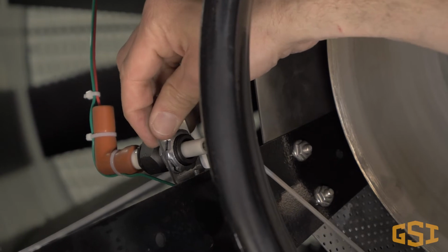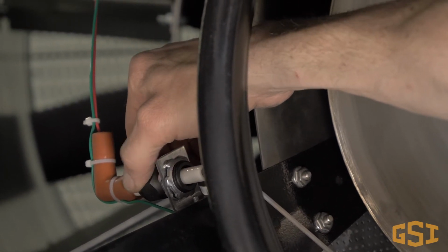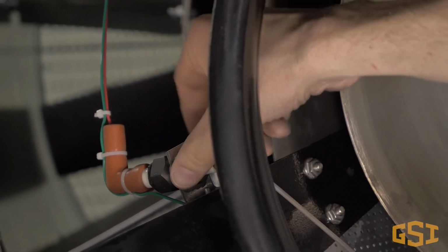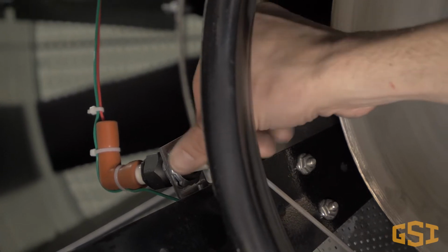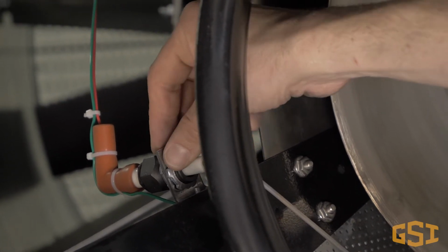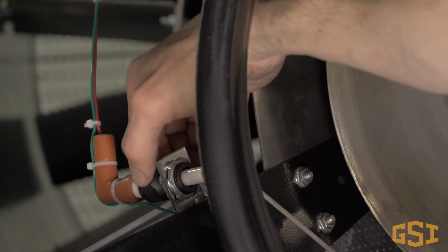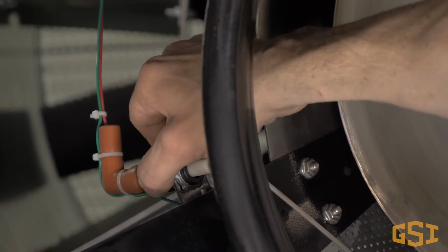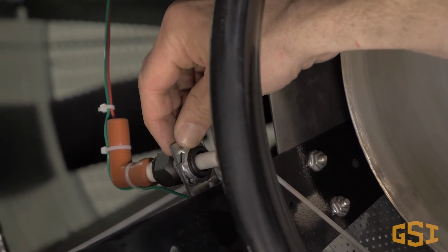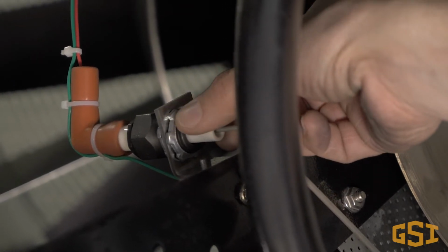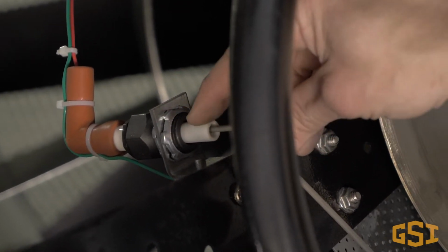Next, check over the flame probe mount. Check that the bolt connecting the flame probe mount to the burner is tight. Inspect the area where the mount is bolted to the burner. Look for rust or anything that could cause poor connection. If you find any rust buildup in this area, it is a good idea to remove the mount, clean the entire area, and then replace the mount.